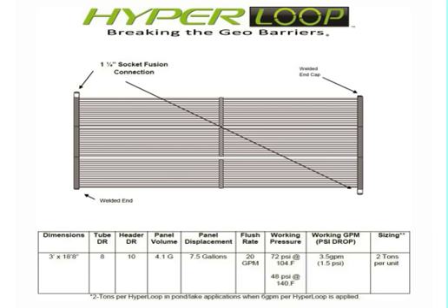I have a 5-ton heat pump on 3 of these, so I'm a little oversized based upon the manufacturer's rating. I have a 5-ton heat pump with a lake plate heat exchanger on one side, my customer with the Hyperloop in the center, and another one with the HDPE coil. So I have 3 5-ton houses and I'm testing 3 different kinds of heat exchangers, and I'll do that for some time so that when I'm asked, I can tell what my experience is.